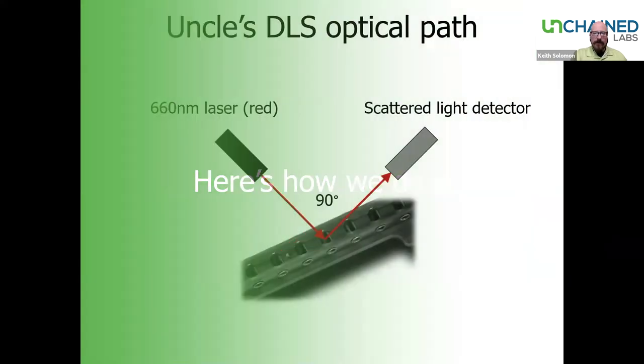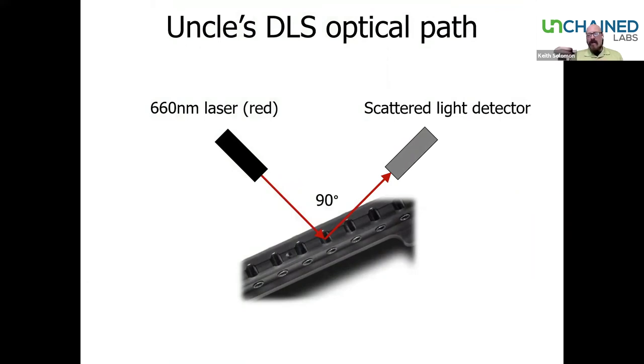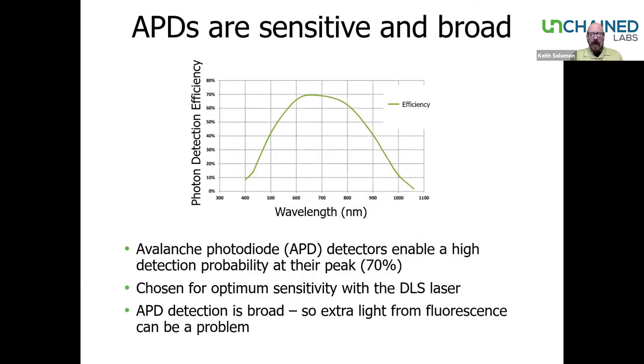So how do we do it at Unchained Labs? We have a 660 nm laser with our avalanche photodiode at a 90-degree angle. We don't have to worry about separating incident light from scattered light because we have a right-angle detector. Avalanche photodiodes are used in the industry because they have fantastic integration speeds and wonderful photo efficiency — around 70% or even higher. They're very sensitive and can be configured to be particularly sensitive for red lasers, making our APD work perfectly well for a 660 nm laser.